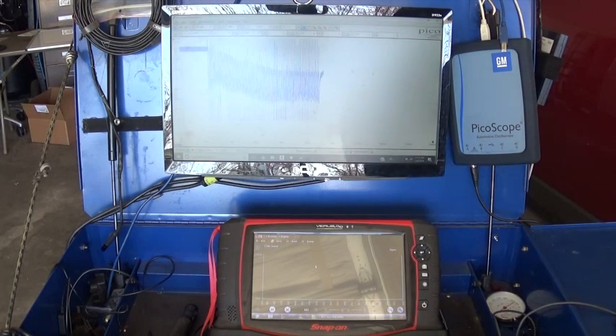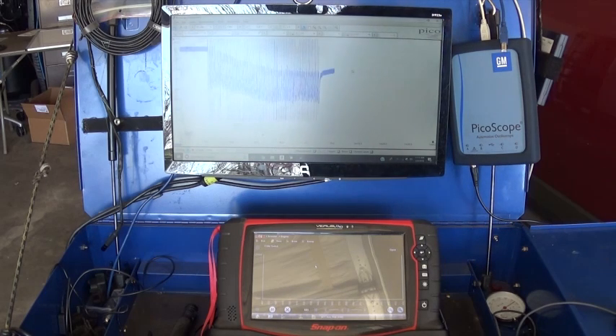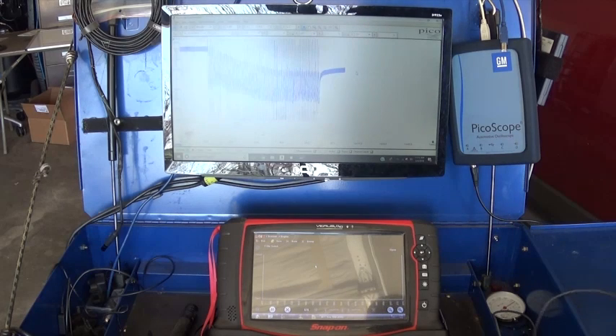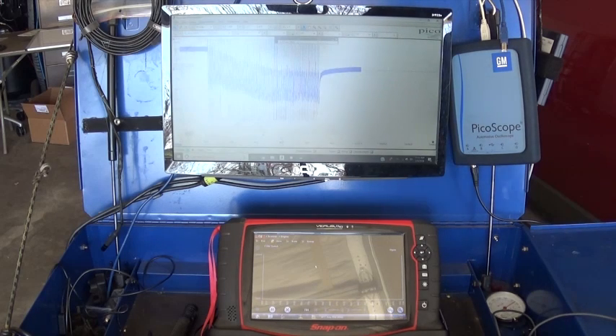I'm going to let go and see if we're holding vacuum. As we can see, my switch is still open. It should close now - we're around a little below 2 inches of water and we're holding the vacuum. So something is not right.